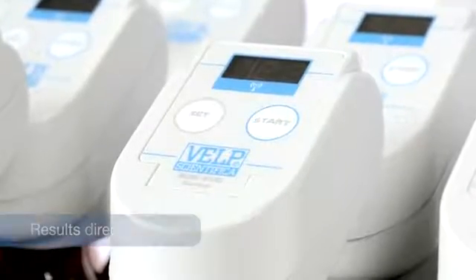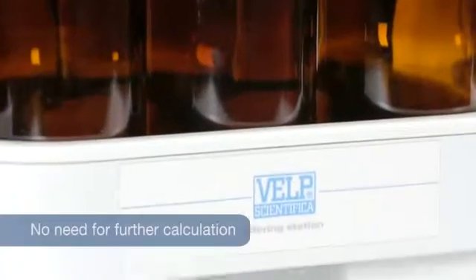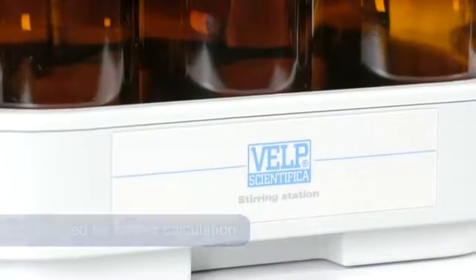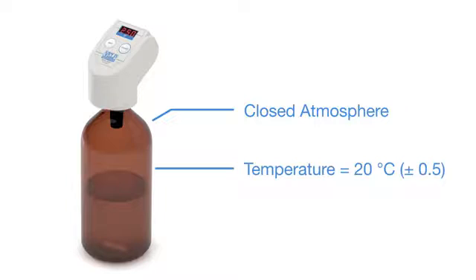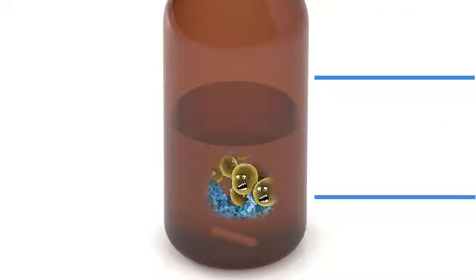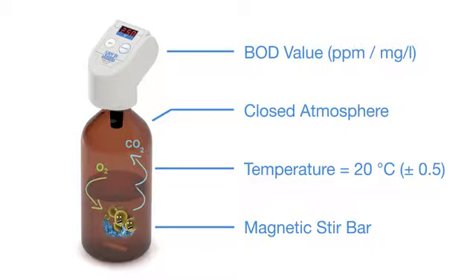The VELP Sensor measures the BOD value directly in milligrams per liter with no need for further calculation. It uses the respirometric method in a closed atmosphere at a constant temperature of 20 degrees centigrade and with gentle sample stirring. The measuring principle consists of determining the oxygen concentration at the beginning and end of a measurement period.